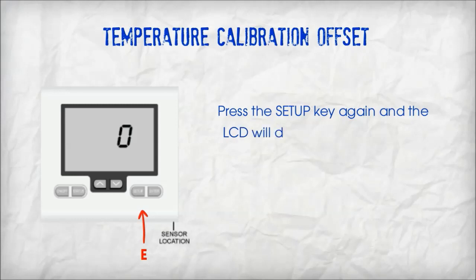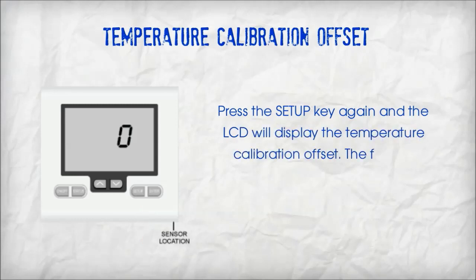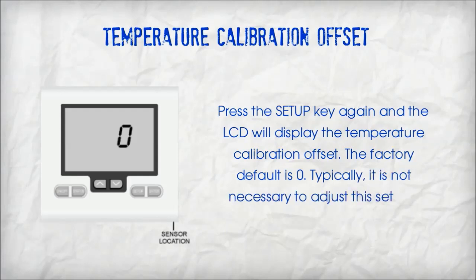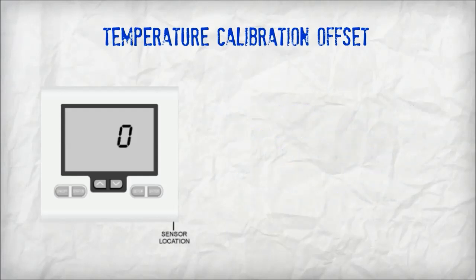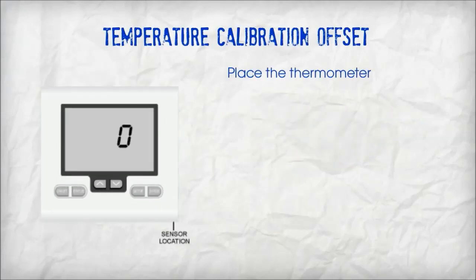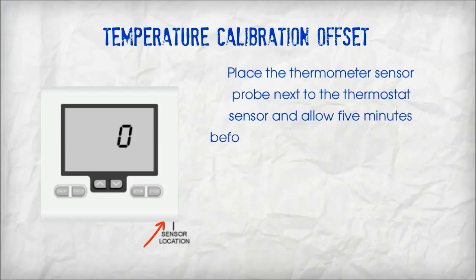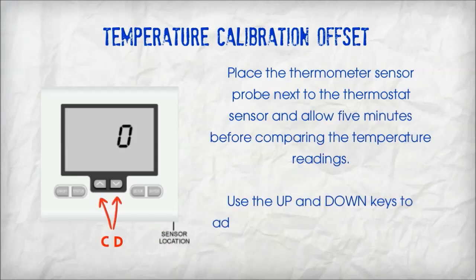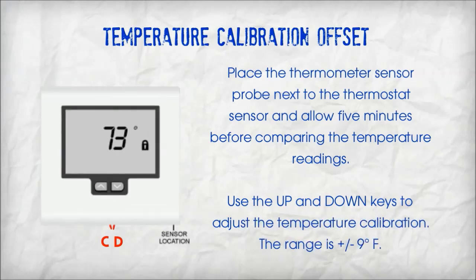Press the setup key again and the LCD will display the temperature calibration offset. The factory default is 0. Typically it is not necessary to adjust this setting. If calibration is necessary, a high quality electronic digital thermometer must be used. Place the thermometer sensor probe next to the thermostat sensor and allow 5 minutes before comparing the temperature readings. Use the up and down keys to adjust the temperature calibration. The range is plus to minus 9 degrees Fahrenheit.